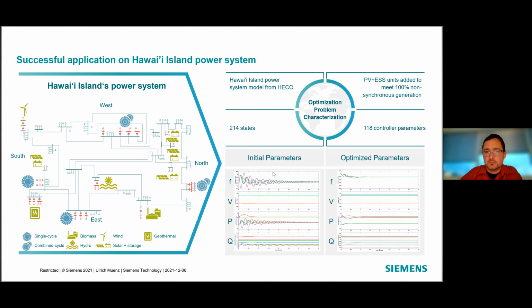At the bottom you see an example with initial parameters that have a lot of oscillations, and then the optimized parameters where these oscillations are suppressed significantly. You can see the frequency, voltage, active and reactive power. So obviously the controller tuning has a huge impact on the dynamics of the system.